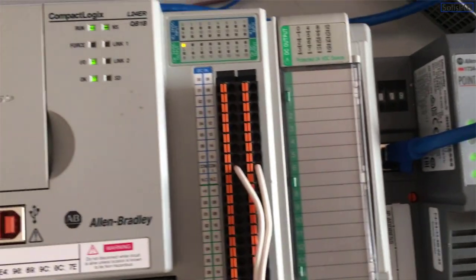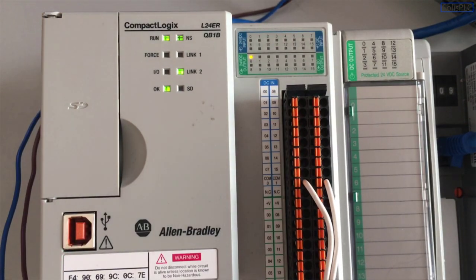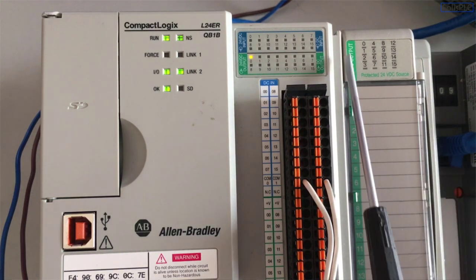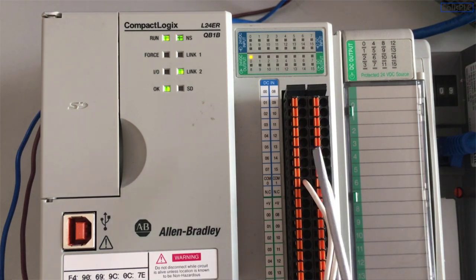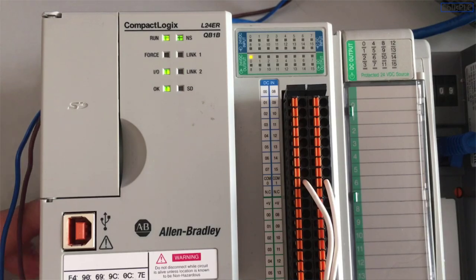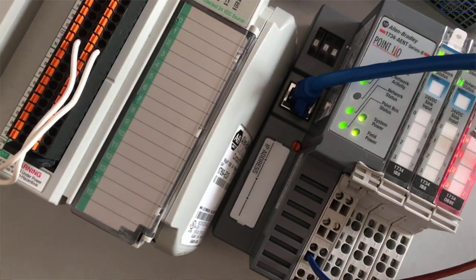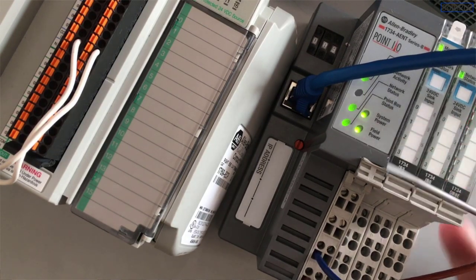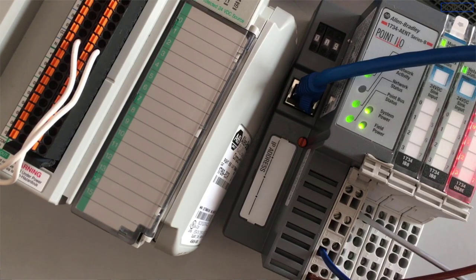Now, as you probably already know, each one of these inputs and outputs can only have a single wire landed on them, and the reason for that, of course, is the physical constraint. So what you want to take advantage of is that whenever any one of these fails, and it will fail at one point or another, you want to be able to physically move your wire, for example, from this output to the next output which is not being used. Chances are, in the field, whenever you design a system, you're not going to be using all the outputs and inputs that you've specified, for that exact purpose of them failing and you being able to replace them. The same thing happens here. You have cards which accommodate inputs and outputs on the point IO, and as they fail, you can simply move the wires from one point to another.